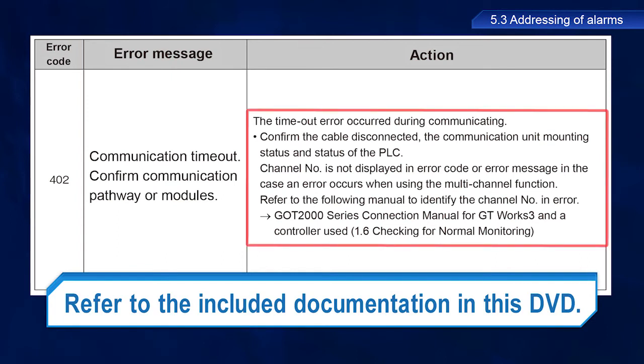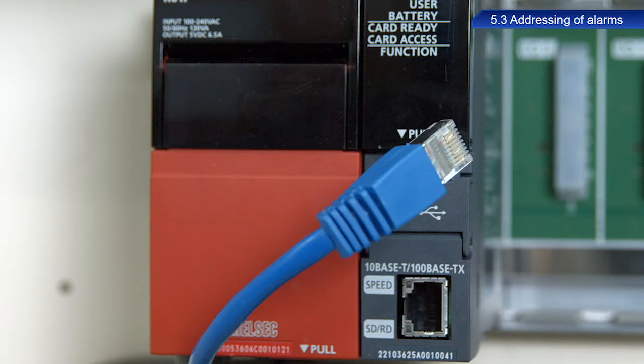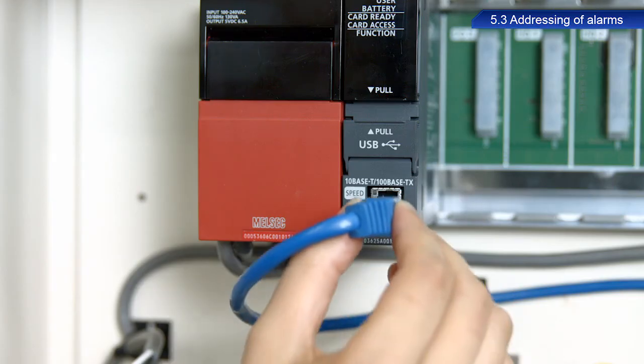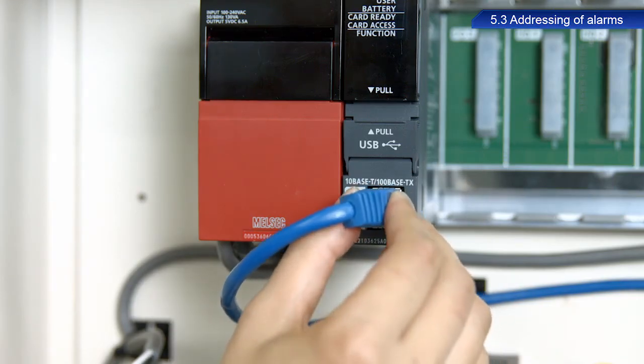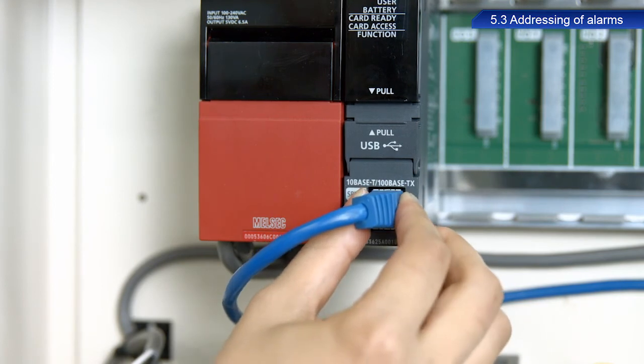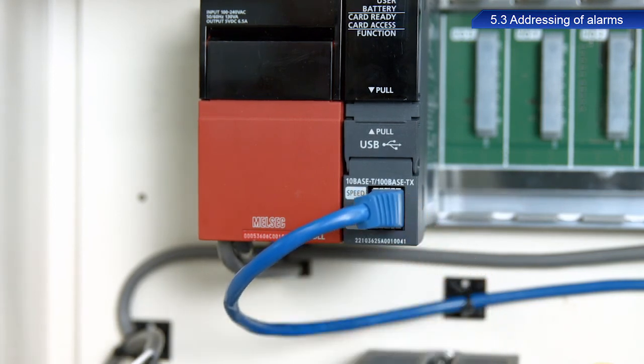As you can see, possible troubleshooting for the 402 error code is cable disconnected, so let's check the cable connecting the GOT and PLC. The cable was not connected correctly, which triggered the alarm. Reconnect the cable correctly. The cause of the error has been resolved.